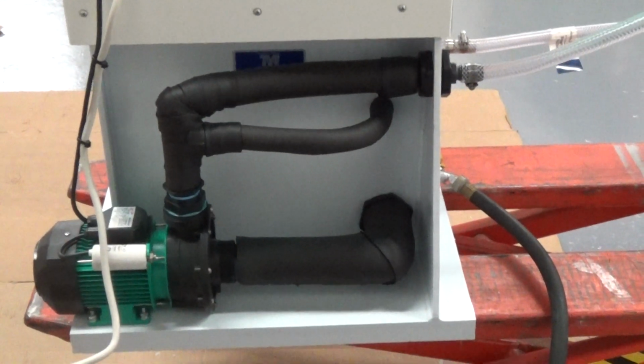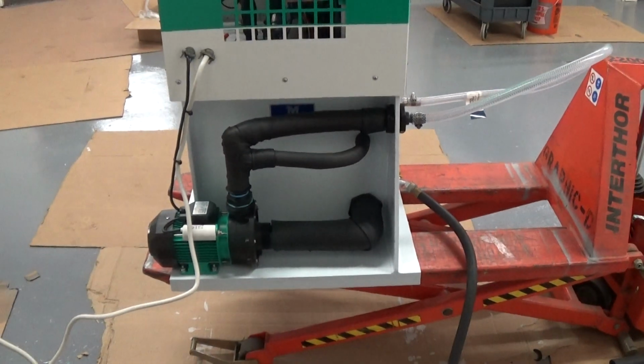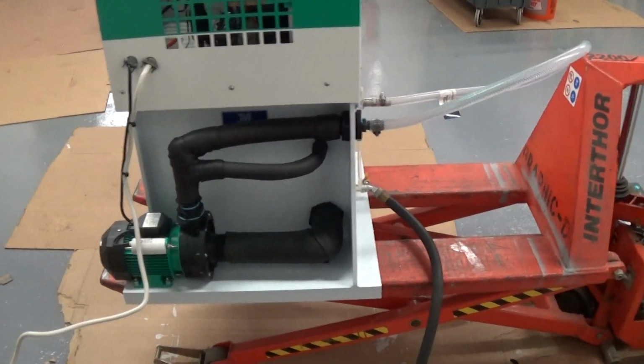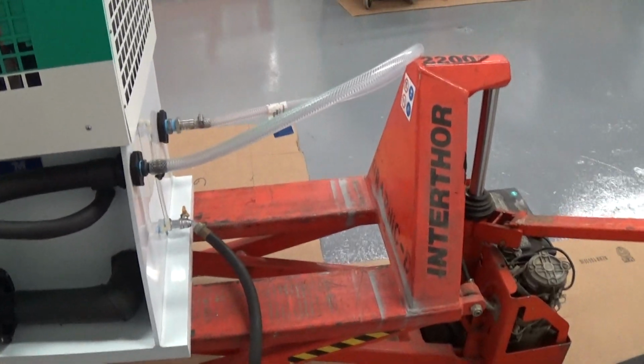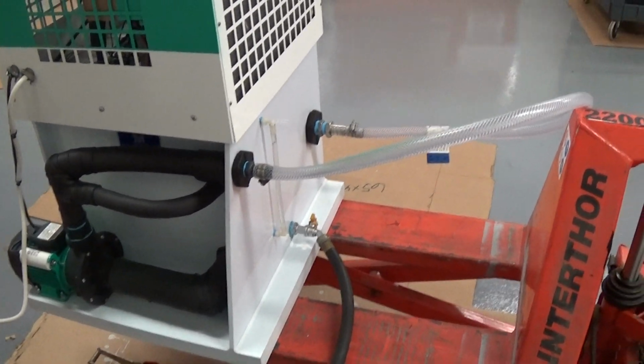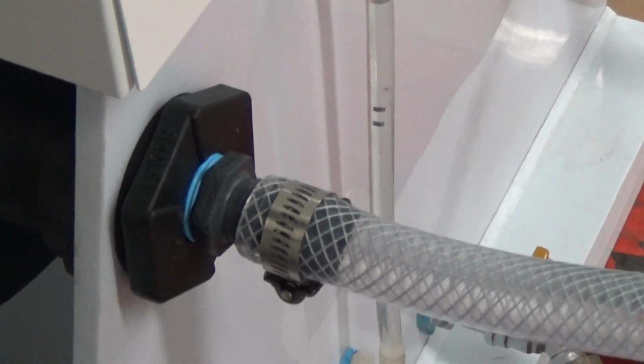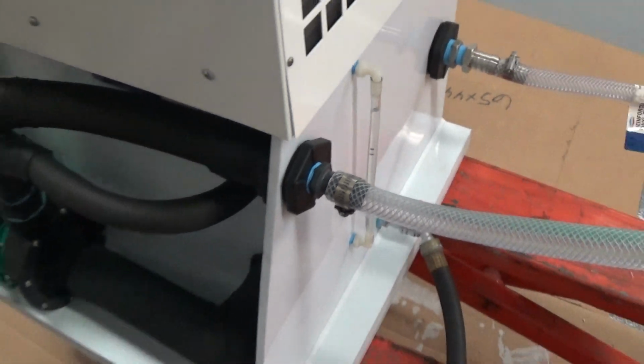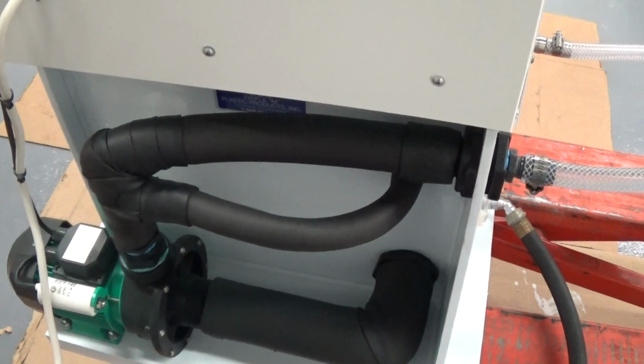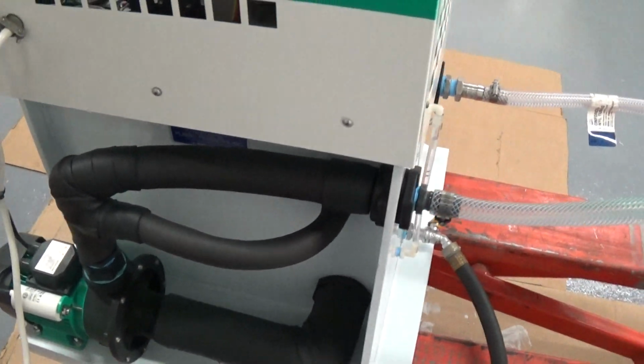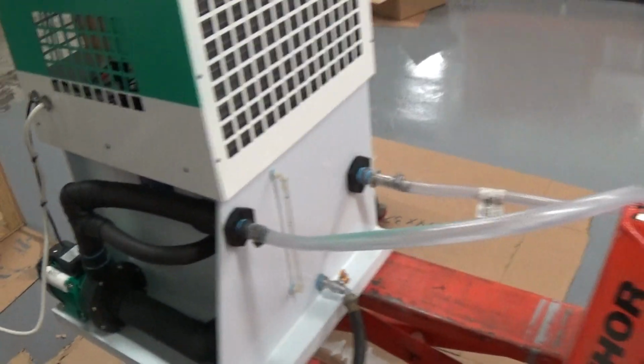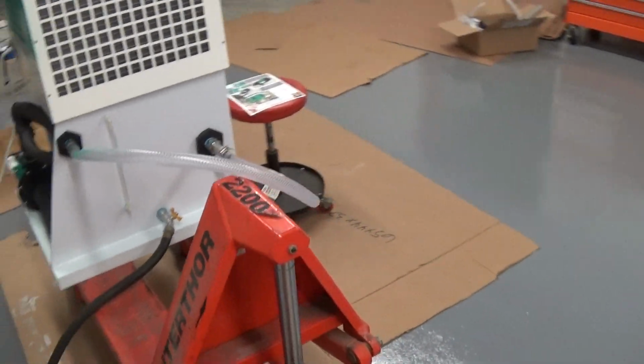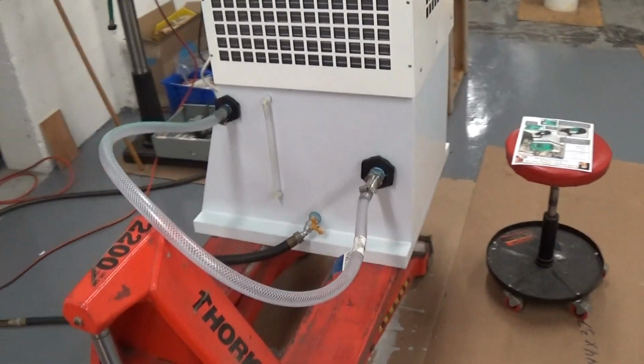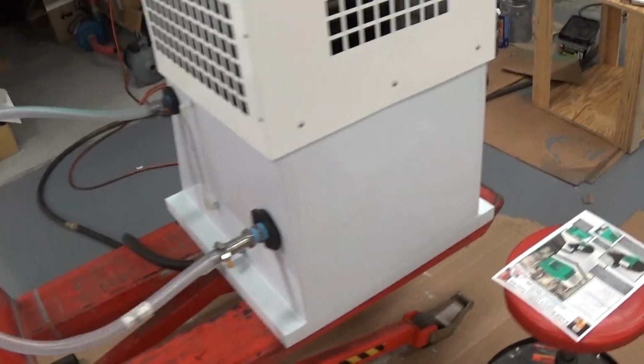It's a small line. But with this chiller here, you should not have any type of bypass in your process piping going out to whatever you're cooling, because you can literally have the output flow, which is here, deadheaded, but we'll still have enough internal flow coming back to the tank and heat exchanger to keep it happy. So that's very important. Don't put in your own bypass, or you'll just be sacrificing flow to your process.